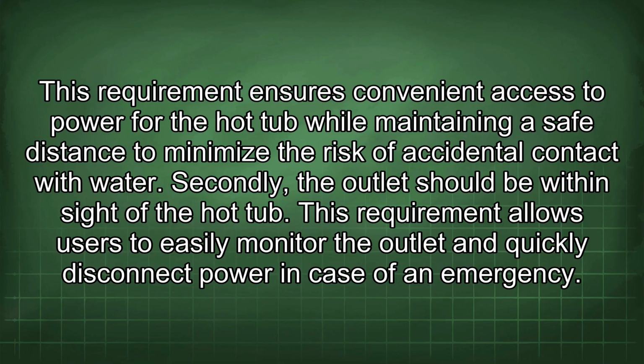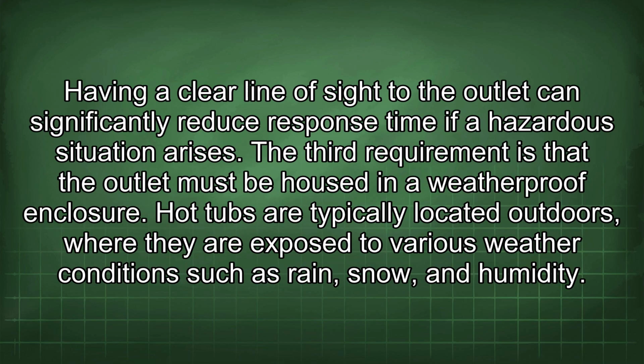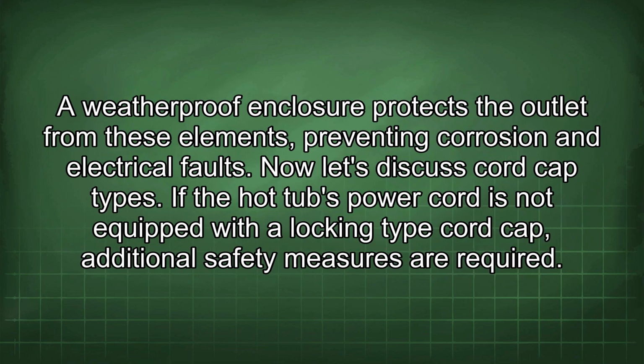Secondly, the outlet should be within sight of the hot tub. This requirement allows users to easily monitor the outlet and quickly disconnect power in case of an emergency. Having a clear line of sight to the outlet can significantly reduce response time if a hazardous situation arises. The third requirement is that the outlet must be housed in a weatherproof enclosure. Hot tubs are typically located outdoors, where they are exposed to various weather conditions such as rain, snow, and humidity. A weatherproof enclosure protects the outlet from these elements, preventing corrosion and electrical faults.